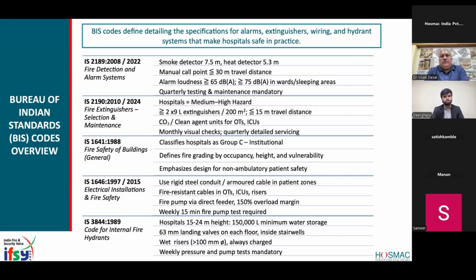Yeah, that is correct. It's a normal range, but it's normally designed on a coverage area. So the coverage area has to be calculated, and accordingly, the smoke detector should be spaced out. But normally, it comes to around 7 to 7.5 meter. Okay, and heat detector should be 5.3. That's the system, yeah.